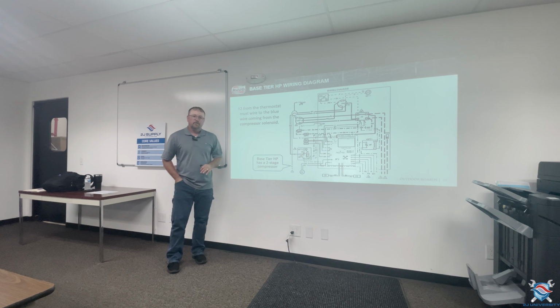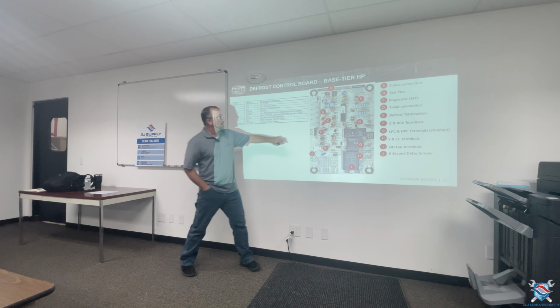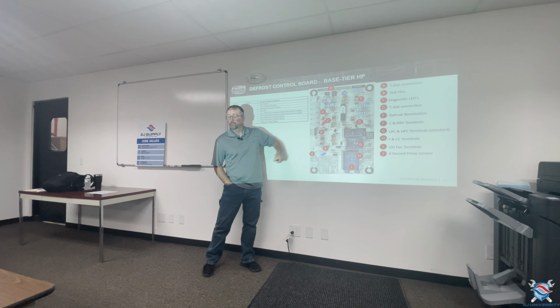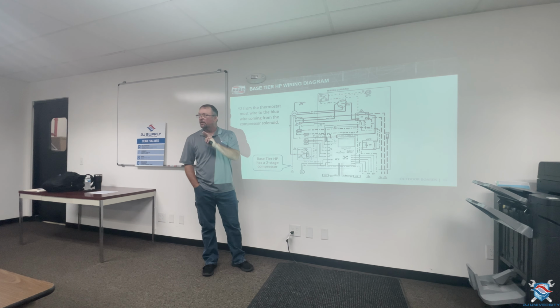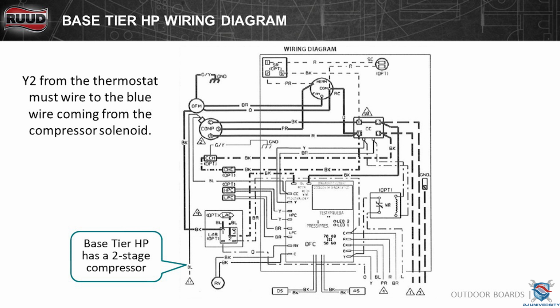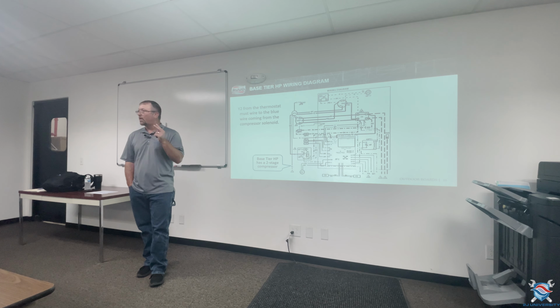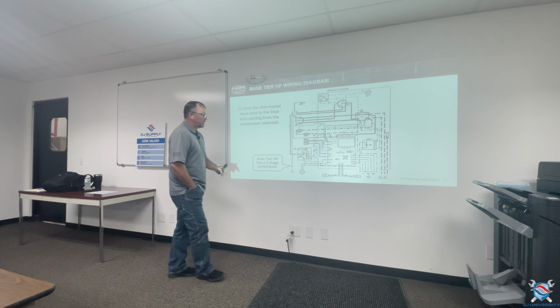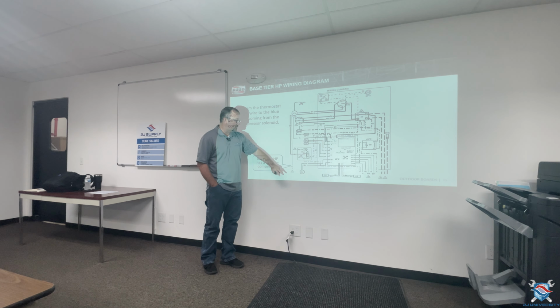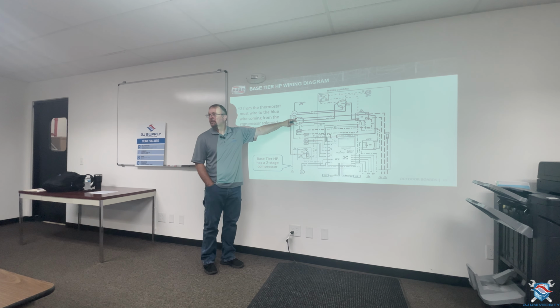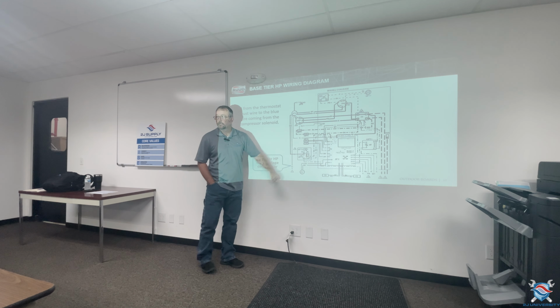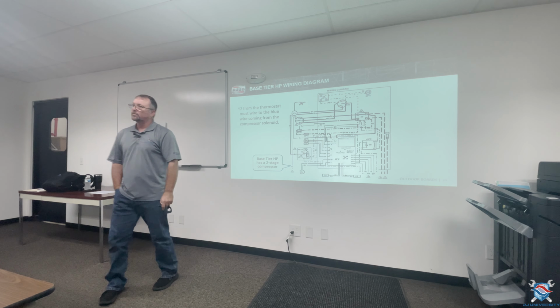On the base tier units, instead of adding Y2 to this board, because those are 2-stage units on your base tier heat pumps, they've added this blue wire that comes in there and it's dangled. And I get this question probably once a week. Guys will call me and they're like, what's this blue wire hanging here? That is your 2nd stage. So that is your Y2 call. Basically, all it does is when you energize Y2 from the thermostat in a 24 volt application, it's going to energize your solenoid on your compressor to send it into high stage, and it also sends the fan into high stage as well.